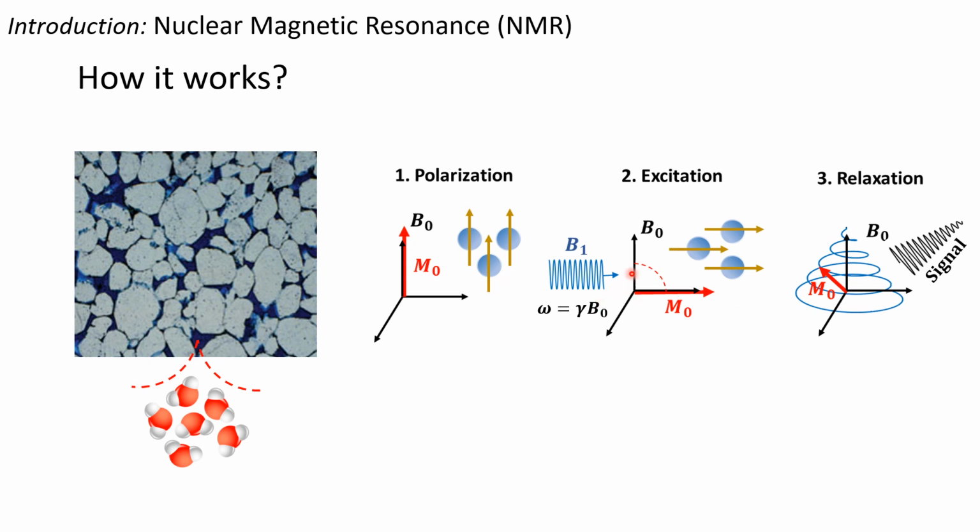So once we turn off that excitation field, that radio frequency pulse, the spins continue to precess about the B naught field for some period of time, but in the end, spins tend to relax back to the equilibrium, which is parallel to the B naught field, and this precession creates an additional alternating magnetic field, which is detected as a voltage on the detection coil.